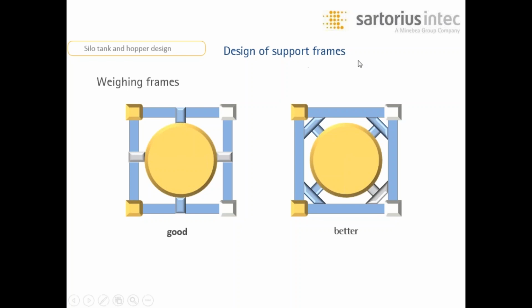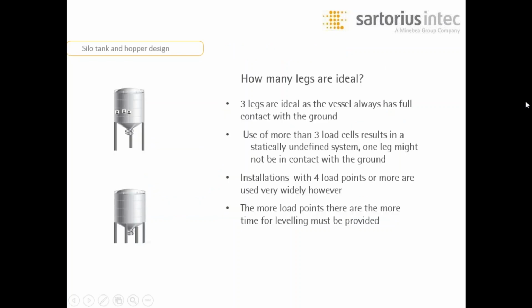All right, how many legs are ideal? The number of weighing modules required is dependent upon the design of the vessel. 3 legs will always be the most efficient design. It ensures the weight of the vessel is equally dispersed across all 3 legs. Although we all know that 4 legs is the most common design. The more legs you have beyond 3, the more installation time is required due to the leveling needed to ensure you have an equalized load on each module.